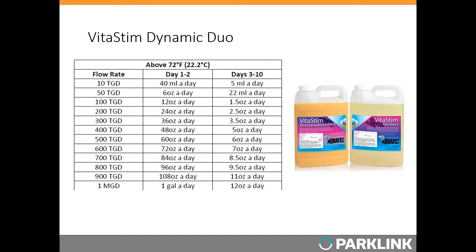Dosing is based on two main factors: influent flow rate and temperature. The warmer the temperature, the less product is required; colder temperatures require more. For an average one-million-gallon-per-day plant with influent ammonia less than 40 ppm at 60–72°F, about one gallon per day of each part — nitrifiers and assimilators — would be added for four days, then a reduced maintenance dose for six additional days. In almost every case, ammonia will drop down to where it needs to be.